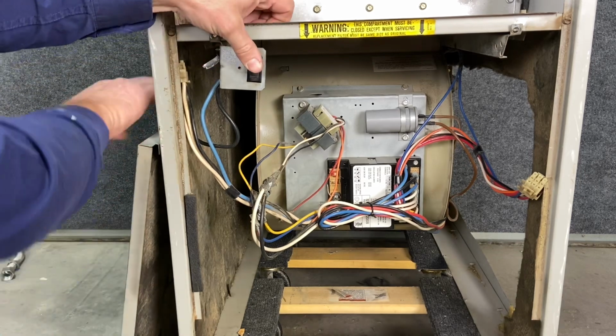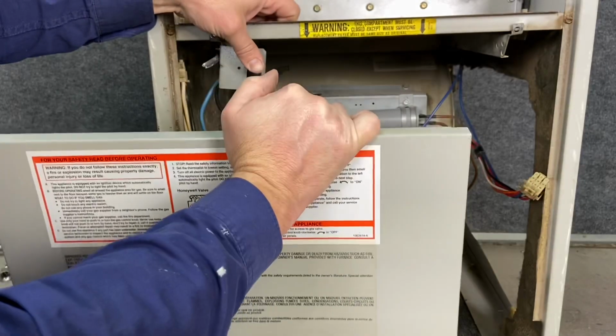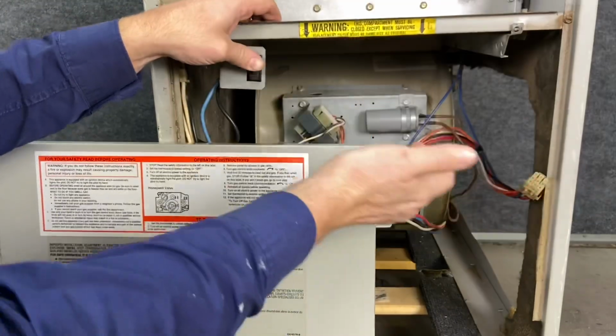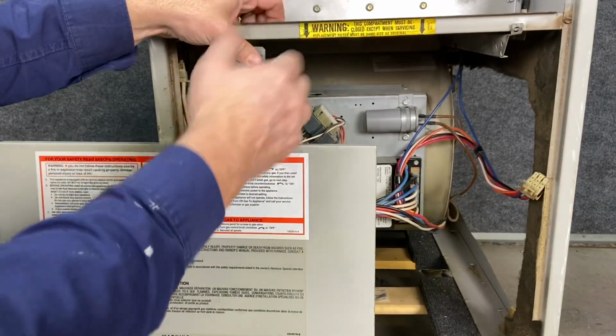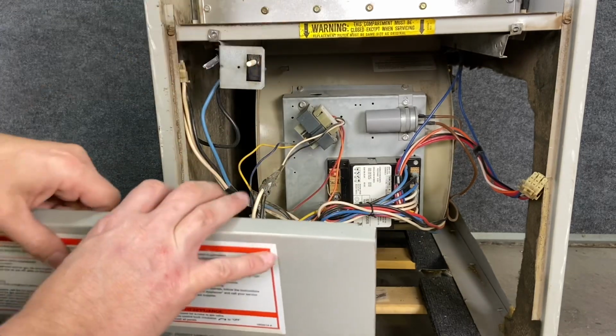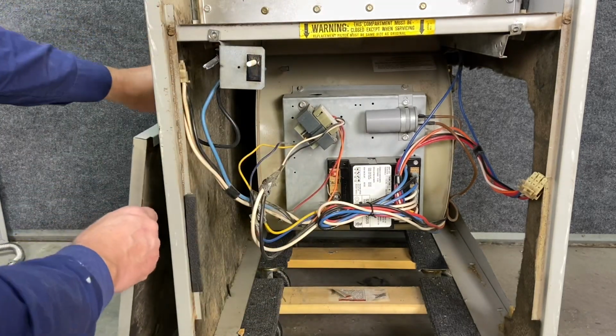Now imagine this door switch is taped closed. The customer opens this to change the filter and leaves the door off. Now they get combustion gases coming in. Well, you've bypassed the safety, and you're liable. So that door safety switch is very important, as well as the door itself.